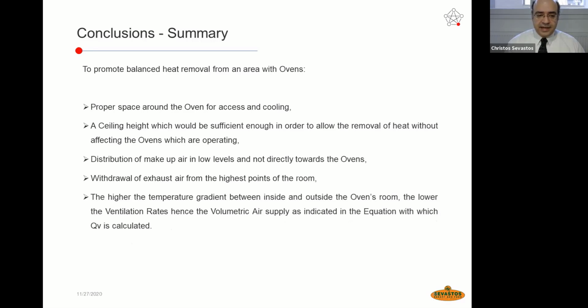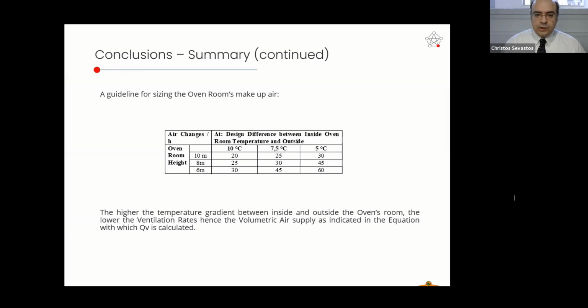And of course, as we have been defining in our equation, the higher the temperature gradient between inside and outside the oven room temperature, the lower would be the ventilation rate, hence the volumetric air supply. This is a general guideline in order for us to define according to our oven room and the height of the oven room and the difference in temperature inside the oven and outside, the outdoor temperature, 10 degrees, 7.5 degrees, 5 degrees. And depending on the room height, 10 meters, 8 meters, 6 meters, those are the air exchange rates, the nominal values, dependent upon the temperature difference, which should be applied in an oven room. Those are the nominal rated values which should be applied in an area where we are applying air ventilation and extraction of heat.